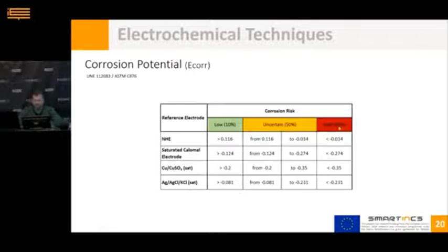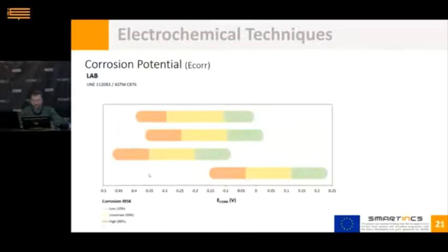As you can see, there is no single criterion for values, but they depend on the reference electrode you are using, since there are several types, we will see later. Here are some of the most used ones. As each electrode has a specific known potential, it is easy to make conversions to refer the measurement to the desired reference electrode. Simply add or subtract the difference between the 2 electrodes to be compared.